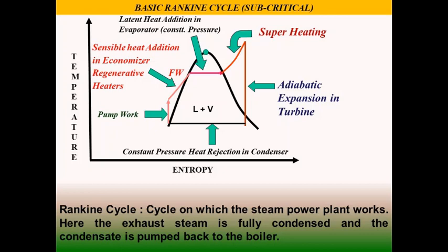There are low temperature superheating and high temperature superheating. Low temperature superheating is done in the primary superheating system. Primary is also distributed in primary LTSH in the second pass and platen superheaters. Subsequently, we have fine tuning and addition of more superheat in the final superheater, and the steam is sent back to the turbine for running the HP turbine.